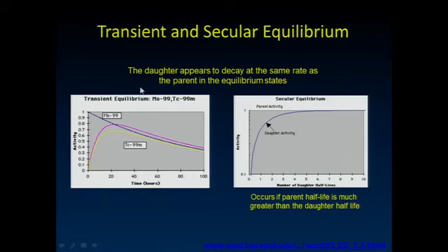And if you have the generator, one of the things that you know that's really nice about it is if you start off with no technetium and just your molybdenum, and you watch after about a 24-hour period, you reach a peak in the amount of technetium that's available there. So you can take all the technetium from the generator and then let the next 24-hour period go on where, again, that amount of technetium was going to rise over time as that molybdenum decays until it's time to elute the generator once again.